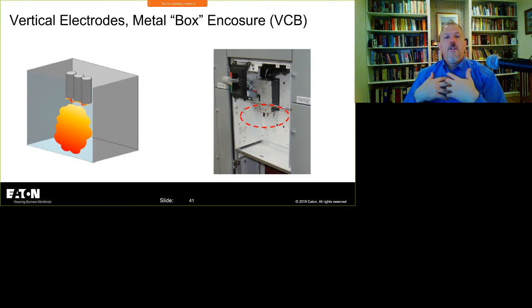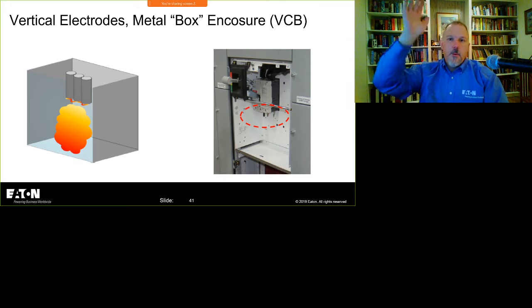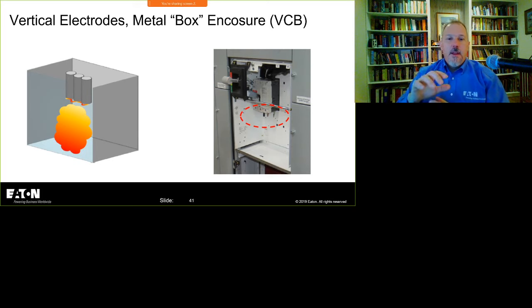You have what they call vertical electrodes in a metal box, VCB, and that's typically your panel board applications, where, when you take a dead front off of a panel board, what are you looking at? You're looking at flat metal buses. You're not looking at the front of those buses. You're looking at the bars. You'll see that copper or aluminum bar perpendicular to you. No, in parallel with you. Yep. So that it's up and down. And that's what you can see there.